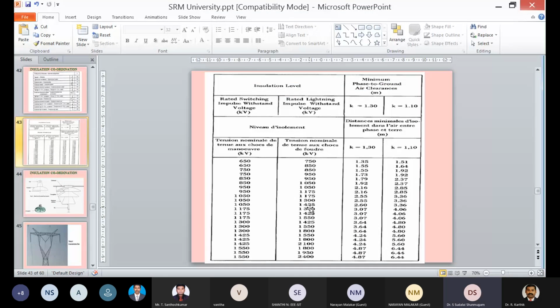So let me consider 1550. What you are seeing is the rated switching impulse voltage and lightning impulse voltage level, and what the distance between phase and ground should be for those levels. Let me consider only one value, 1175. If you go to the standard, you can see 1550 and 1175. At first look, I can tell it is a 400 kV system.